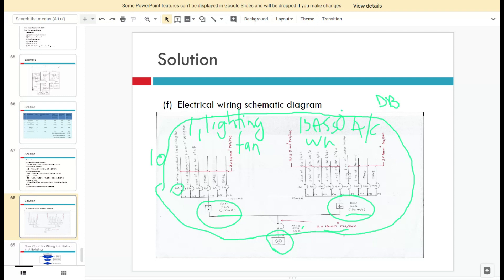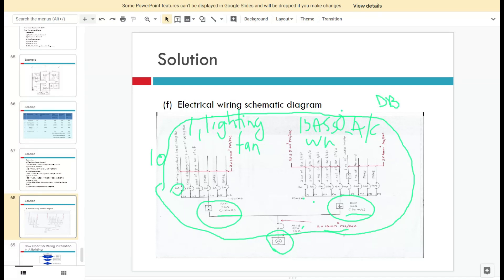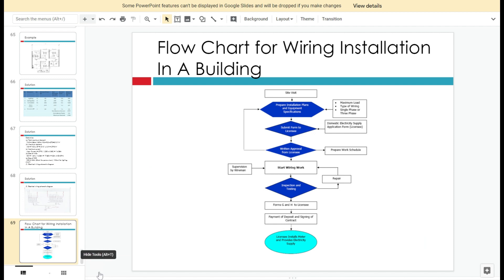For the power side, consider a maximum of three 13-amp SSOs per MCB. For example, grouping them as two, two, two, or three, three, two — it depends on your design but must be economically viable. For the water heater, an additional RCCB or RCD is required with a sensitivity of 10 milliamps, because it is very close to human beings. Then connect the air conditioner, and include two spare circuits. This completes the electrical wiring schematic diagram.